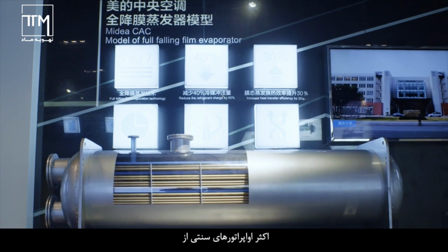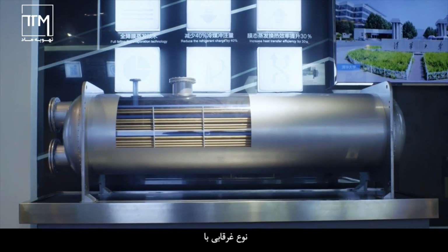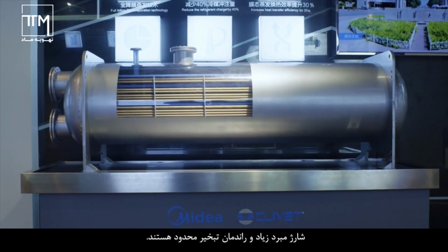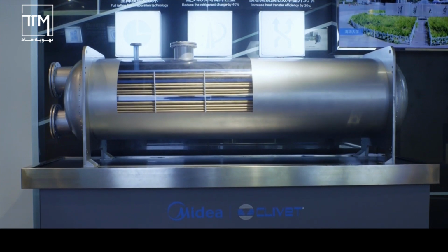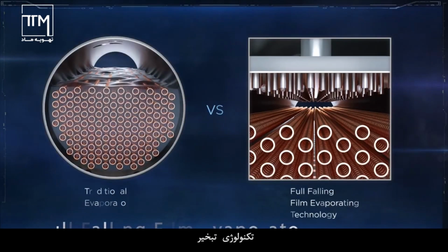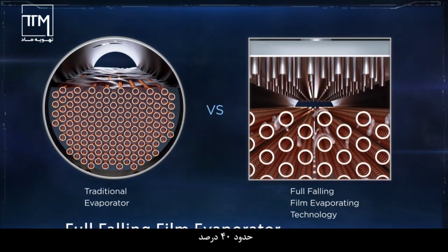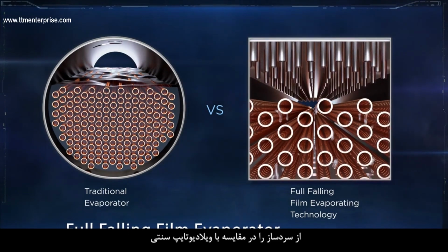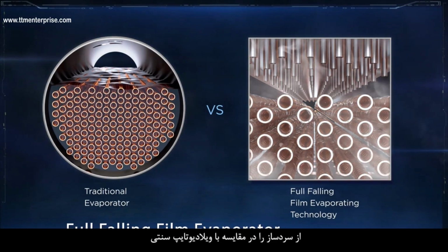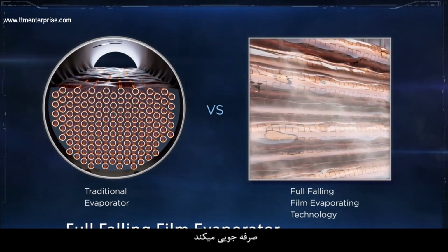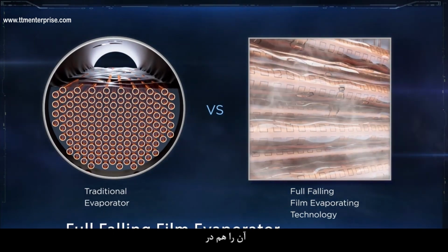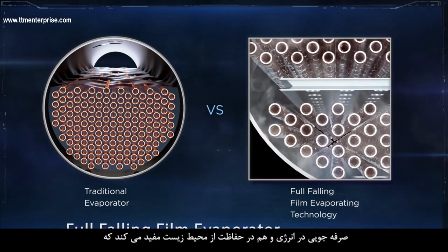Most of the traditional evaporators are flooded type, with a large refrigerant charge and limited evaporation efficiency. Midea's pioneered full falling film evaporation technology saves about 40% of the refrigerant compared to the traditional flooded type, which makes it advantageous in both energy saving and environmental protection.